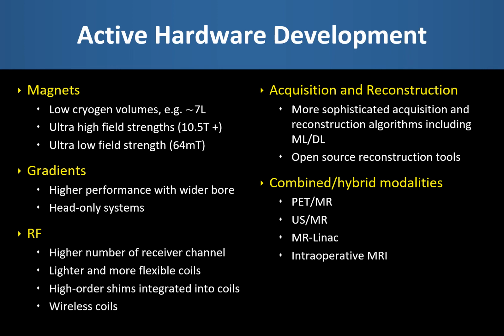This slide is to give you some indication of the current trends and developments in commercial MRI systems. One vendor is now offering a 1.5 Tesla superconducting magnet that only requires around 7 litres of liquid helium to remain superconducting, which makes siting the system somewhat easier as you do not have to have a quench pipe. There are also research and development activities to develop and build ultra-high field magnets at 10.5 Tesla and above. Conversely, an ultra-low field 64 millitesla portable MRI system has recently come onto the market, allowing the MRI scanner to be taken to the critically ill patients that themselves cannot be moved down to a conventional MRI facility.